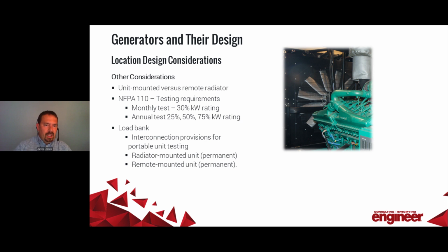There's also the option of doing annual testing. And again, if you're using a load bank because you don't have the building load to actually transfer and meet these thresholds, or you'd rather avoid the outage, the blip in power, specifically in healthcare occupancies or other critical facilities, it's probably best to provide provisions for a load bank, or provide a permanently installed load bank, right? You can always provide a permanently installed load bank that's either radiator mounted on the front of the unit or is remote mounted on the roof or elsewhere outside.